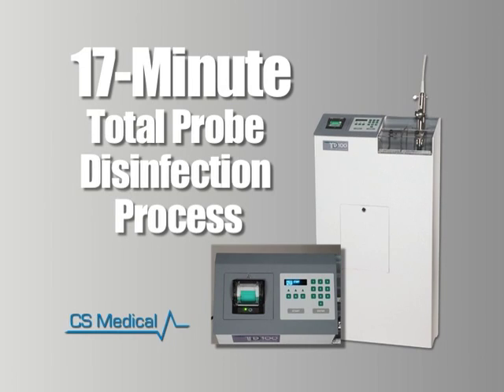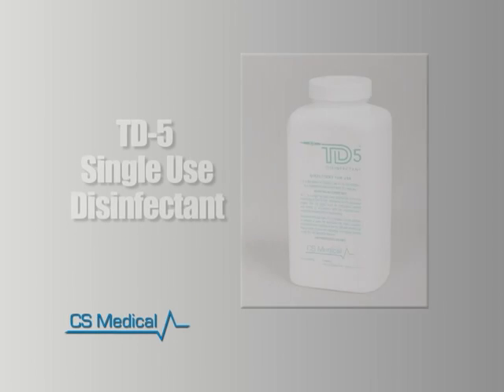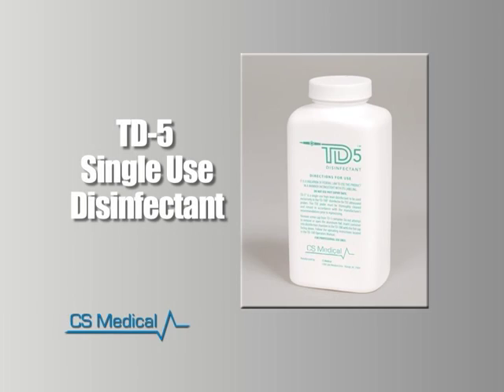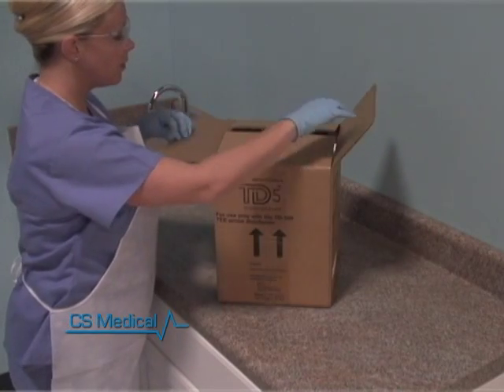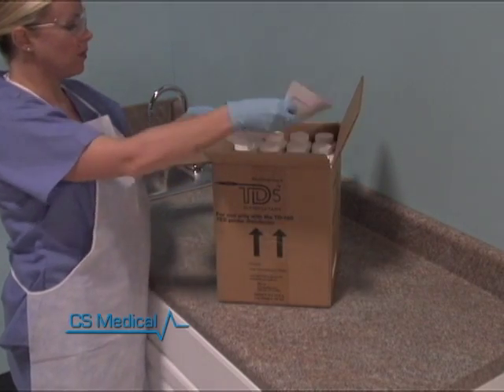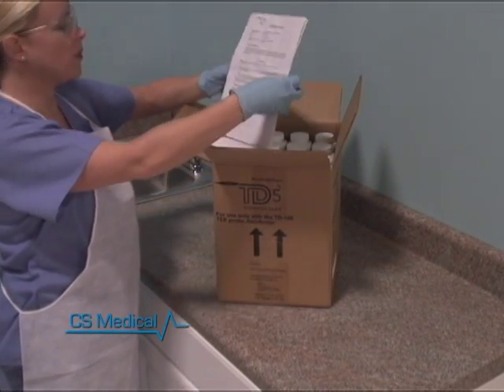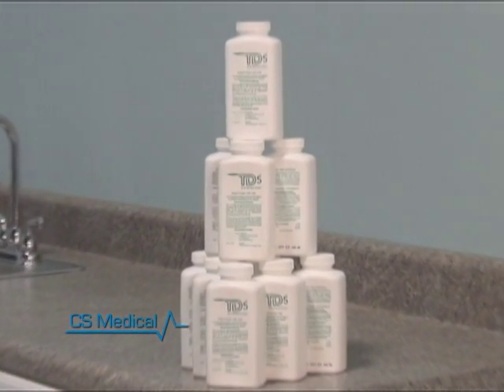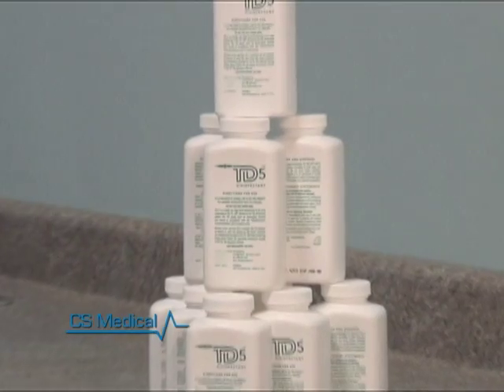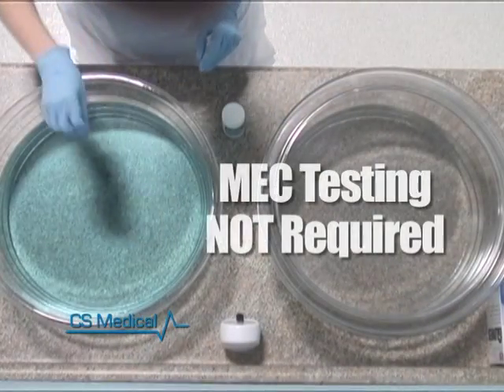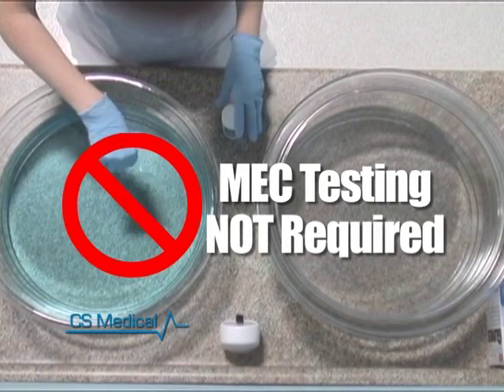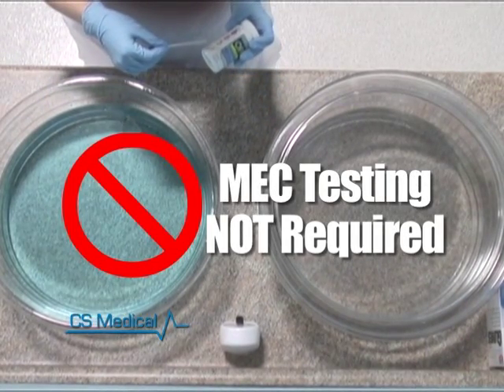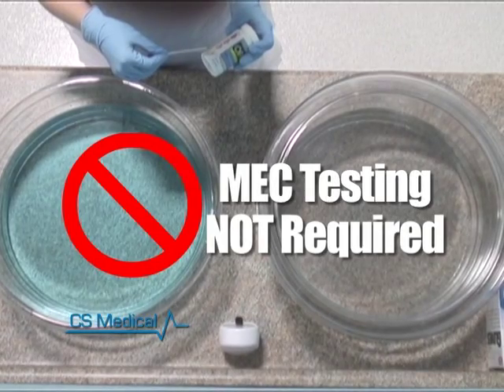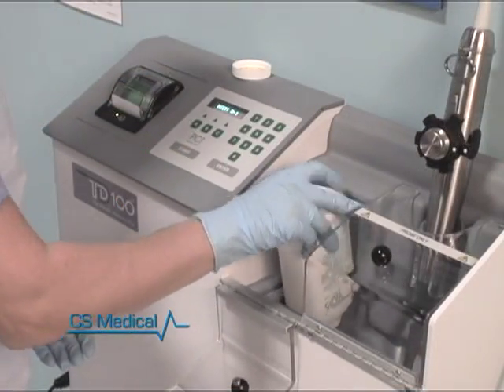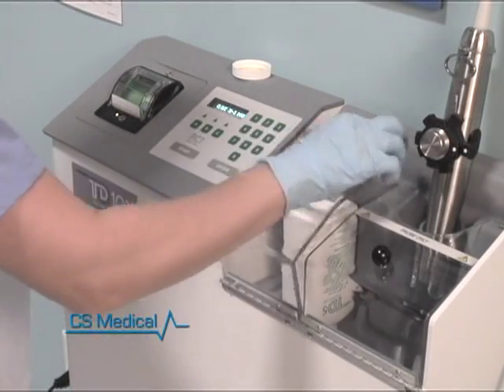While the TD100 is processing the TEE probe, let's talk about the TD5 disinfectant used in the disinfection cycle. The TD5 is a single-use glutaraldehyde-based disinfectant, specifically designed for the TD100 and TEE probes. The TD100 uses a fresh bottle of TD5 for each disinfection cycle. This eliminates the need for MEC testing. MEC testing is required with any method that reuses the high-level disinfectant, automated endoscope reprocessors, and basins alike before each usage. The TD5 bottle is pierced inside the TD100, thus minimizing the potential for splash, spills, and vapor exposure.